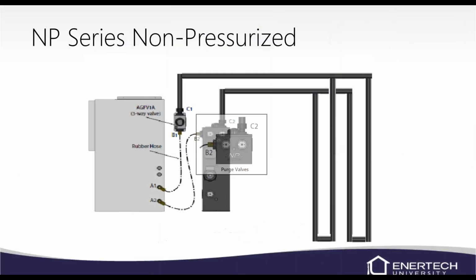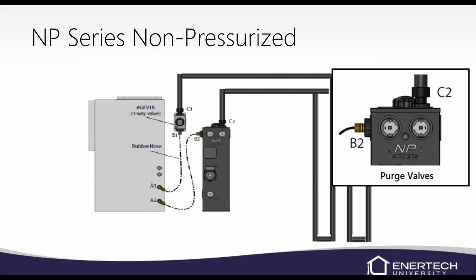Non-pressurized flow centers. So we use the NP series normally now. I think we can still get some others too, but this is the one we've been using. You can see those dotted lines on the left picture. That's your rubber hose kit. And we're also showing a three-way valve, which is basically a flush block. Obviously, you're going to need to flush, so you'll probably need that three-way valve. It's an insulated flushing block.